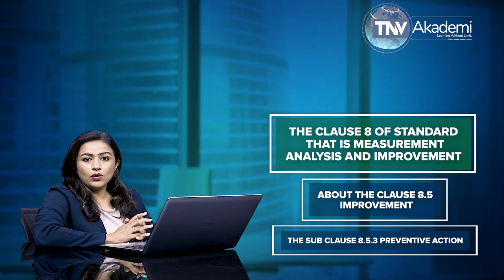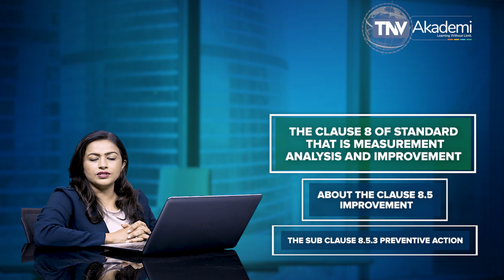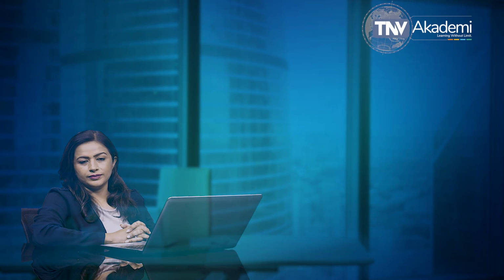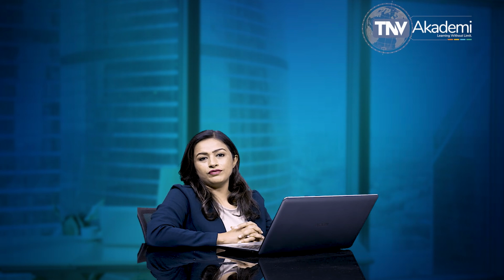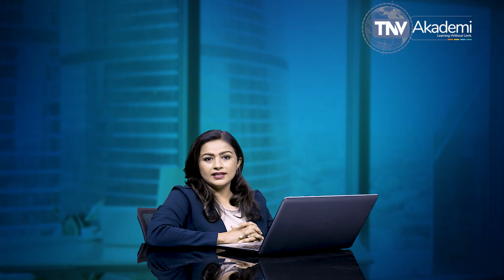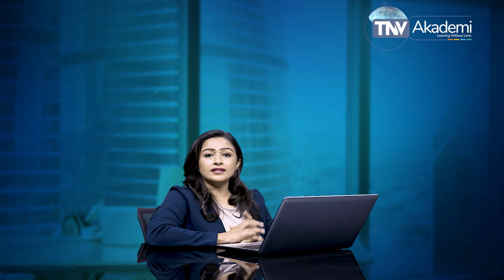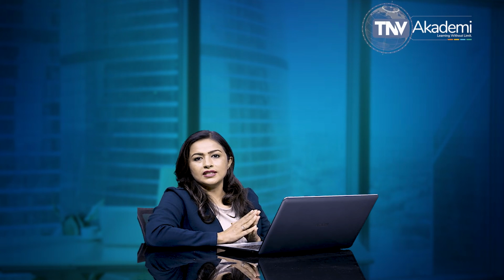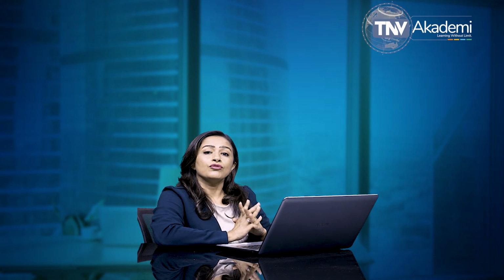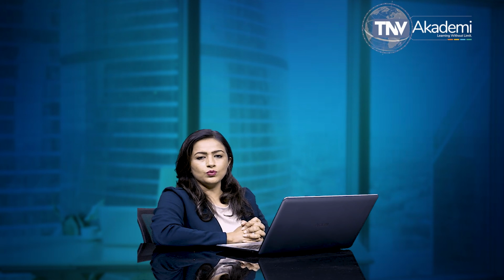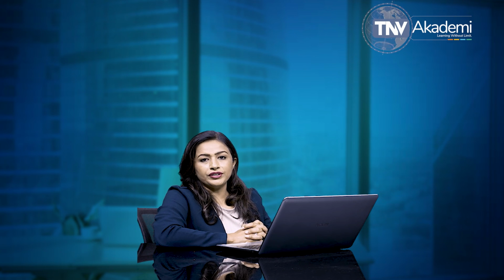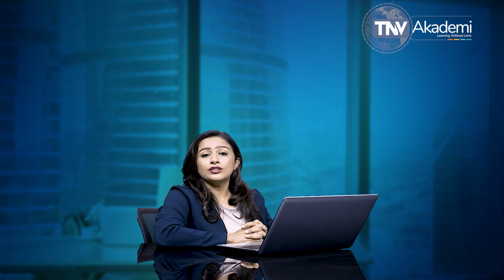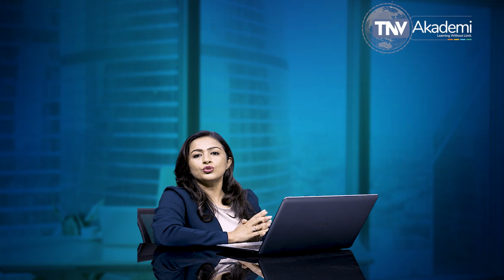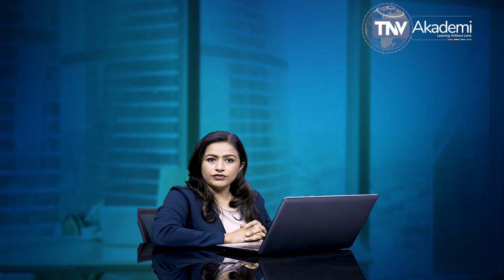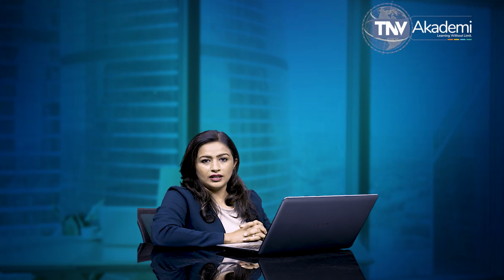This clause specifies that the organization must maintain the records of the results of any investigations and of action taken to meet the requirements of the standard. Friends, we have finished all the clauses of ISO 13485:2016 Medical Devices Quality Management System. The standard ISO 13485:2016 also provides a correspondence between ISO 13485:2016 and ISO 9001:2015 under Annex B and a bibliography for more detailed information about various fundamentals, techniques, and requirements. You can see here on the screen the correspondence between ISO 13485:2016 and ISO 9001:2015 and the bibliography at the end of the session, and could explore more about the standards.